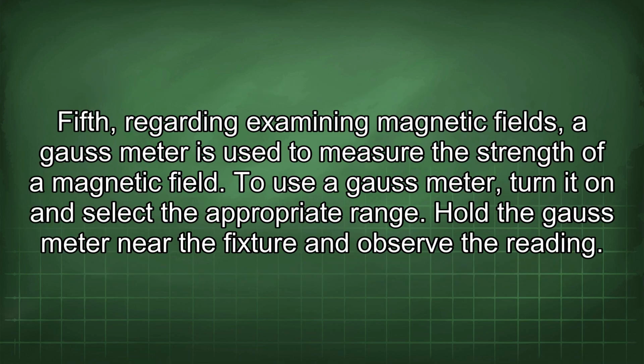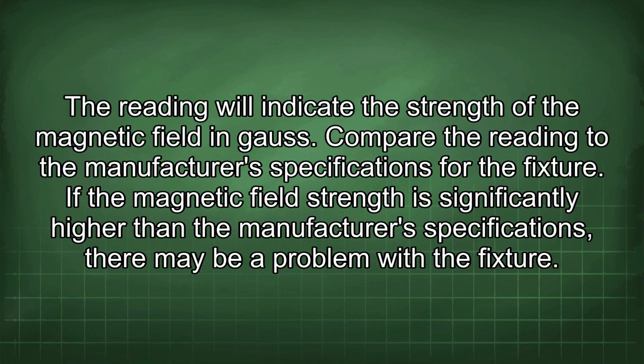Fifth, regarding examining magnetic fields, a Gauss meter is used to measure the strength of a magnetic field. To use a Gauss meter, turn it on and select the appropriate range. Hold the Gauss meter near the fixture and observe the reading. The reading will indicate the strength of the magnetic field in Gauss. Compare the reading to the manufacturer's specifications for the fixture.